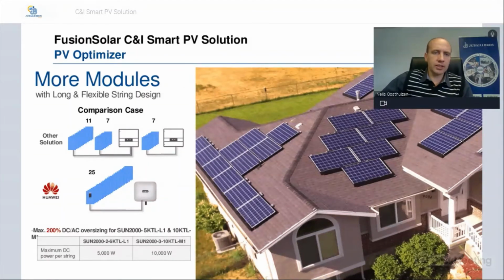In this next one, we're again looking at PV optimizers, with more modules and a long and flexible string design. Typically, looking at maximum DC power per string, if you just have an unoptimized solution, you can only go up to a maximum of 5 kilowatt. But if you're using the Huawei optimizers, you can go up to a 10 kilowatt design. The 2 to 6 KTL is a specific reference example for a residential single phase, and the 3 to 10 KTL M1 is the 3-phase residential range.